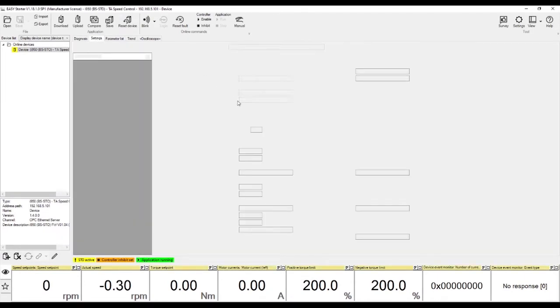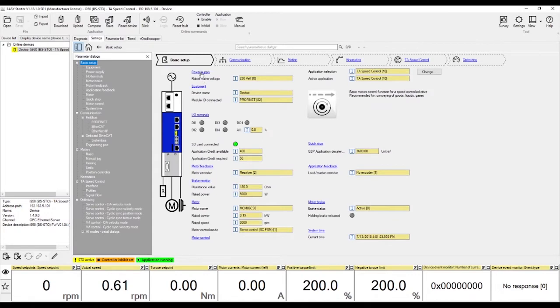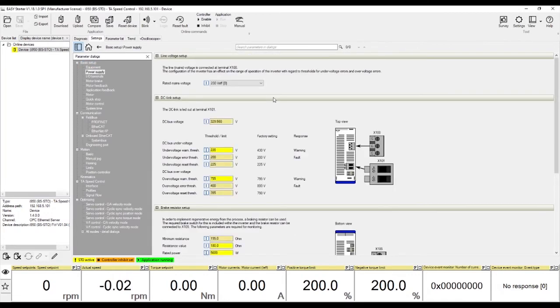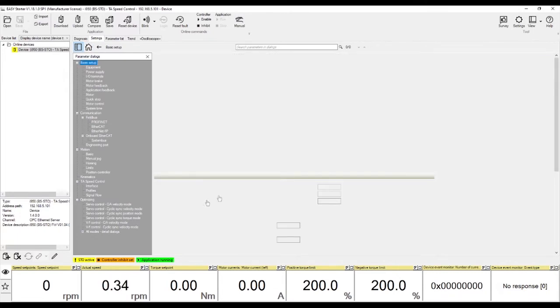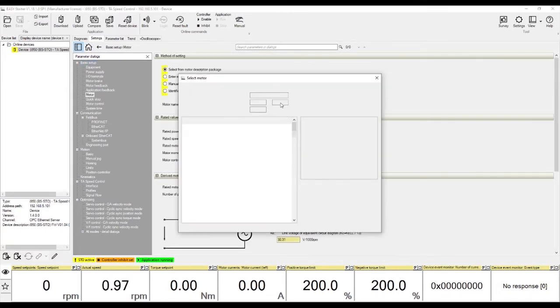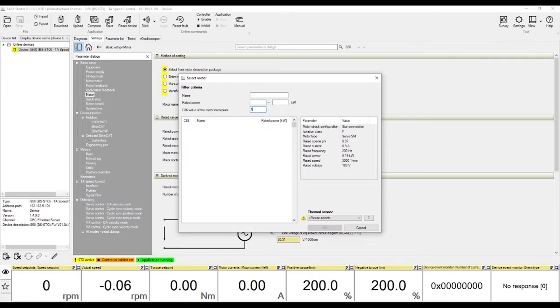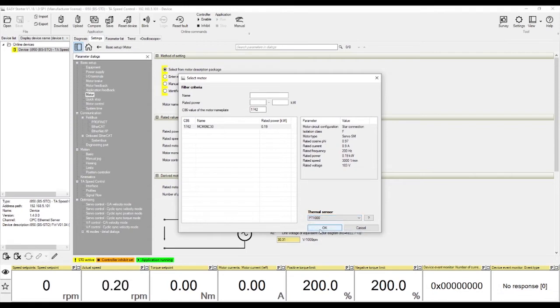Go to Settings and click on Power Supply. Change the rated mains voltage and the under voltage and over voltage threshold to your appropriate values. Then click on Home. From here, click on Motor and input the motor characteristics. If you have a Lenze motor, you can type in the C86 code found on the motor nameplate and the correct motor parameters will be added automatically to the program.